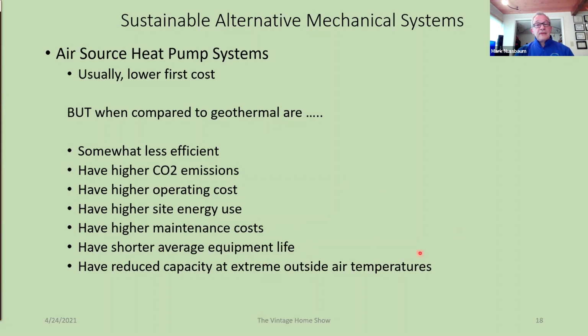And with all heat pumps, we have a reduced capacity as air temperatures drop or go up. It works in both directions, but we're most concerned about it in the heating season. Air source heat pumps have gotten a lot better about having good capacity when we get into the winter months, down to real low temperatures. But there is a degradation of capacity. You need to make sure you get one that will give you everything you need at the lowest temperature you expect to have. Because when you're not using the heat pump, it switches over to electric resistance, which is the most expensive way to heat your house. So you want to just be aware of that situation.